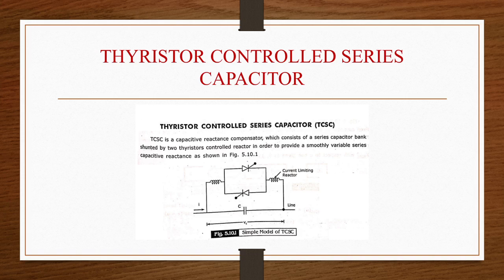SVC is classified as TCR, TSC, and TSR, which we have seen in detail. Now let us see about the thyristor-controlled series capacitor, TCSC. TCSC is a capacitive reactance compensation device which consists of a series capacitor bank with a thyristor-controlled reactor in order to provide a smoothly variable series capacitive reactance, as shown in the figure.